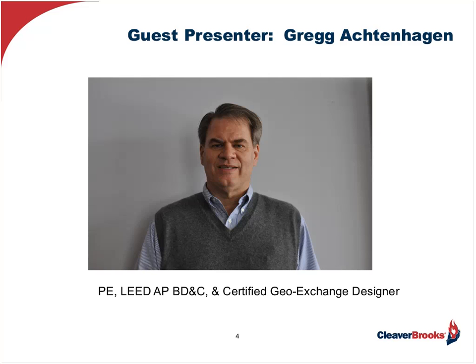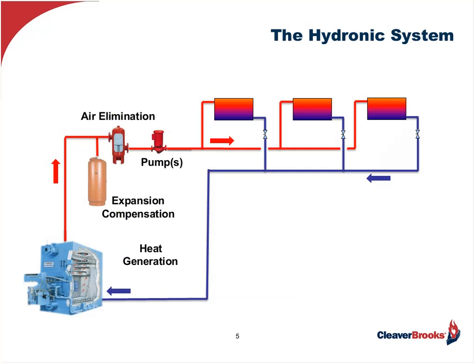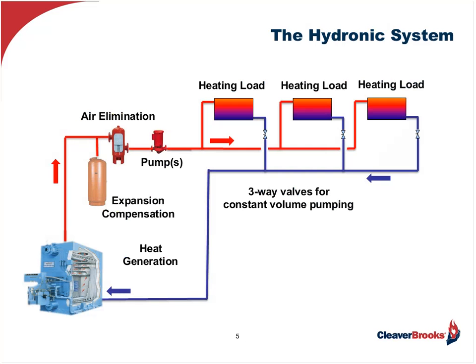Thanks, Steve. Well, to get started here, I want to make sure we go in the right direction. I'd like to start off with just talking about a basic hydronic system so we're all on the same page when we're talking about terms and all the different components. A basic hydronic system is going to consist of your heating load. These are your terminal units out in the space. Fin pipe radiation, VAV reheat coils, or larger loads such as air handling unit heating coils. They'll typically have some type of control valve. In this case, we're showing the three-way control valves off of there, so this is a constant volume system. You then have the heat generation, or in our case, the boiler.